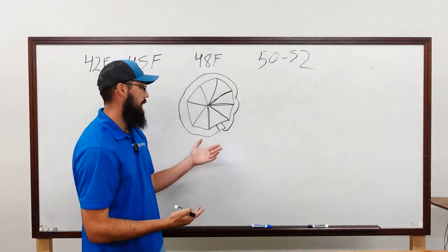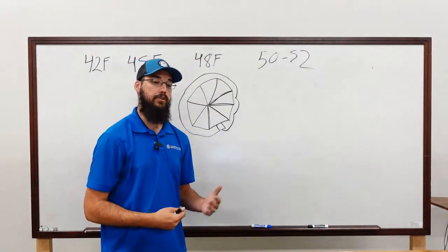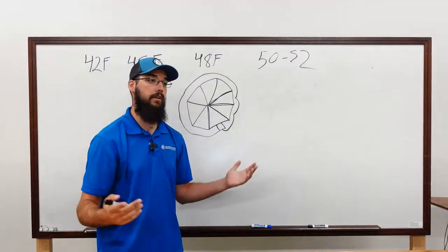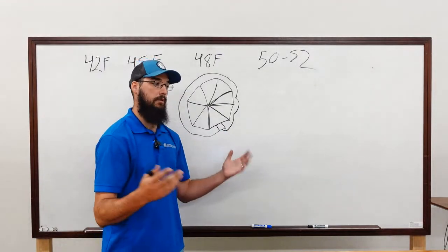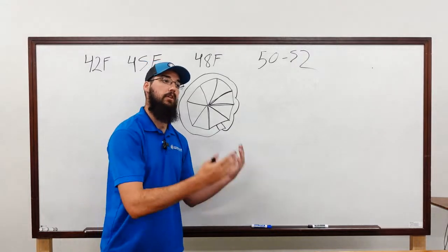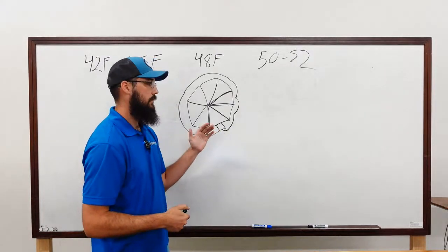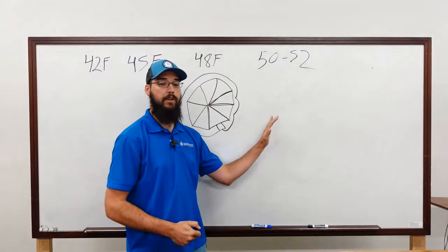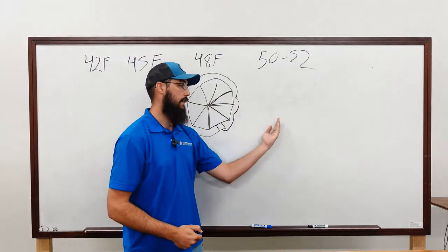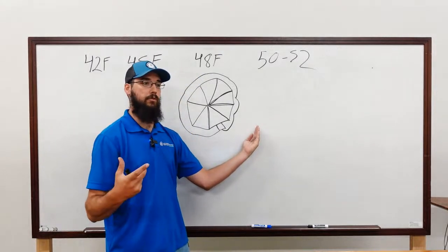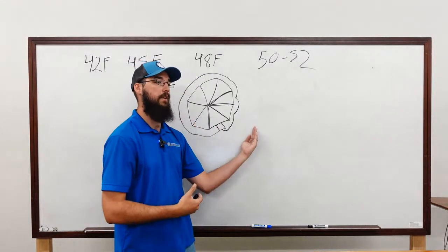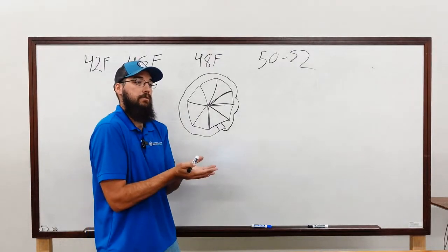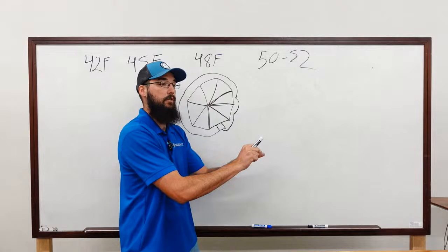Now, if you are having some kind of water issue, or if a water issue popped up while the machine was online, say your variable speed flow just dipped too low for any condition, right? You're going to start seeing that suction limiter as a means of keeping the machine on without having to shut down. Because your variable water flow became too low, it's going to force that machine to back off on the load to try to get that suction pressure up. First, it's going to stop it. It's not going to let it go any further.